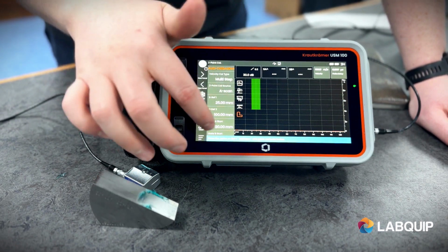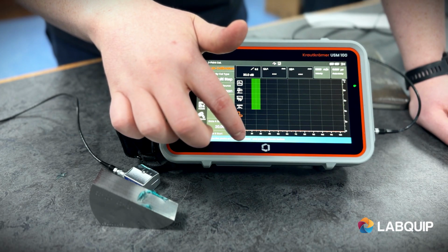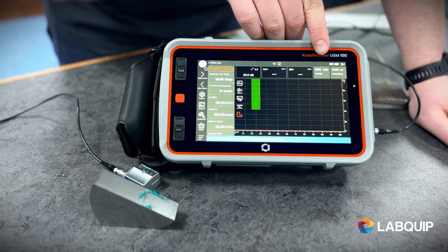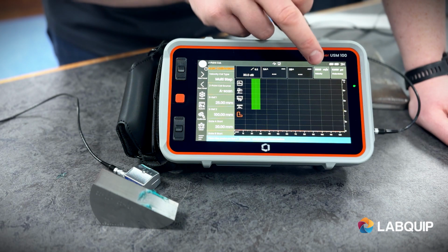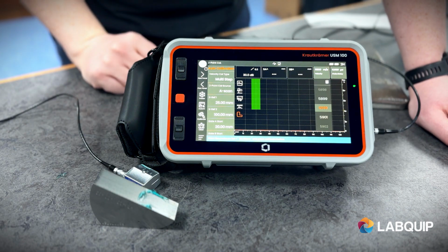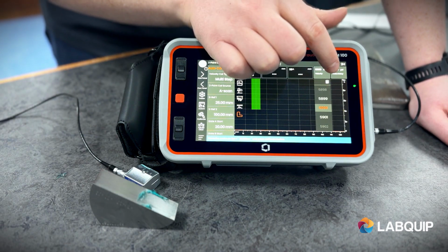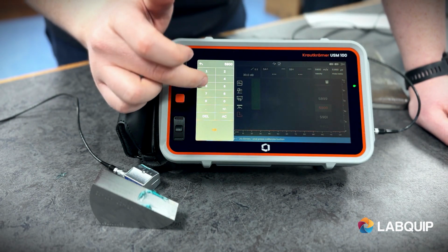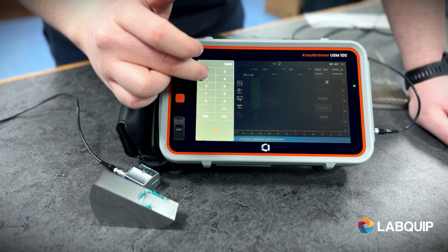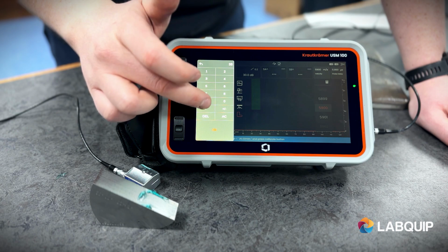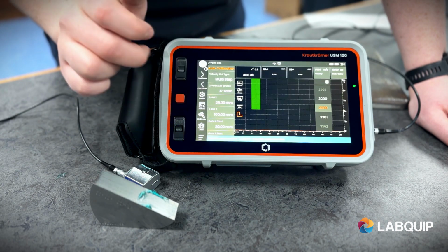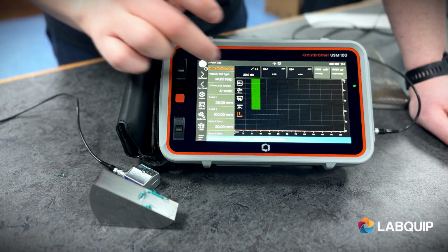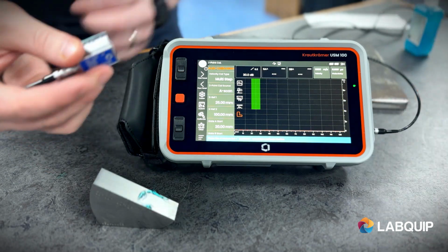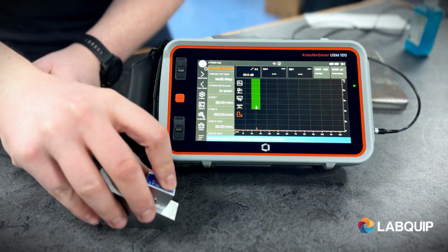So the unit comes up, place the probe in 25 mil and hit calibrate. Now, I never set up my velocity in the last page, but that doesn't matter. I can do it now by tapping on velocity over here. Velocity of steel is in around 3,300. So I'm just going to put it in, but when I calibrate the system, it will get this a bit more accurately. So place the probe on the cal block.